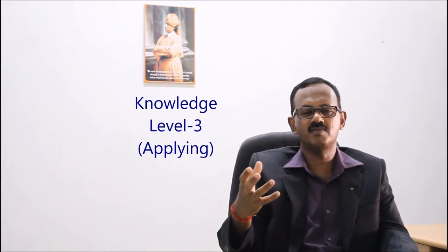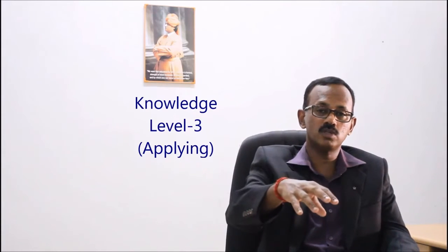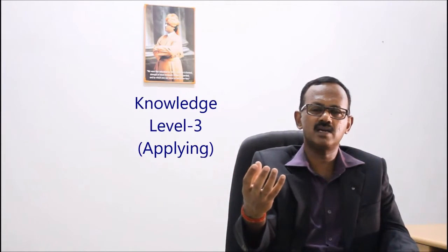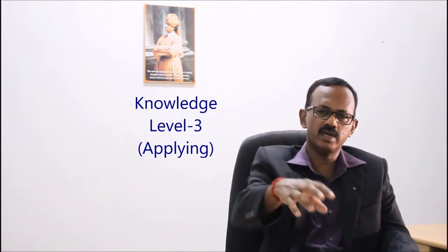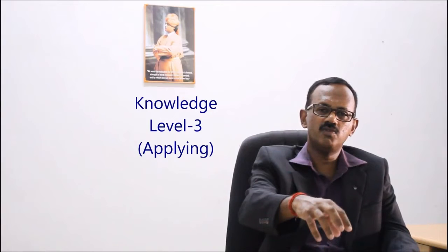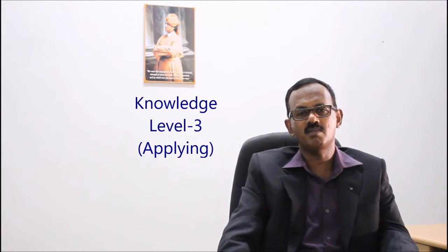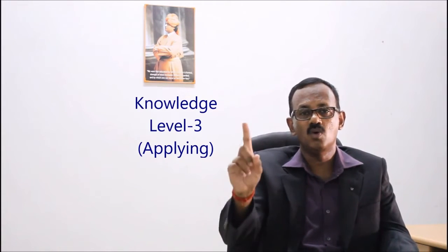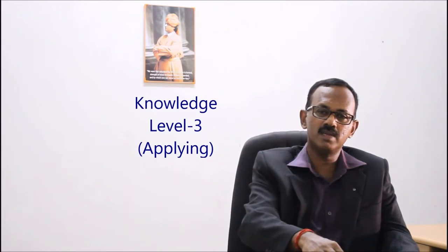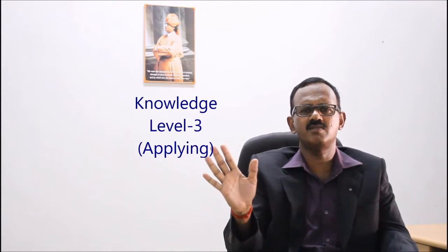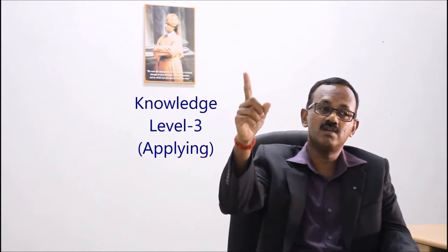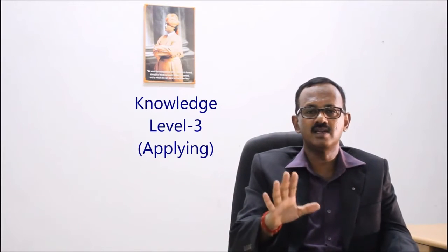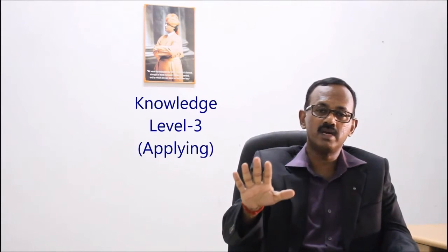Now, by the definition of calibration, when a known input is being given, that is, you take a 1 kg weight, and it should either be a primary standard or a secondary standard. Let us say you are going to take a 1 kilogram weight, and if you are going to place it on the weighing platform, automatically the reading in the digital scale is expected to be 1 kg, because you are placing either a primary or a secondary standard. That is, the exact weight will be there. Now, if the display shows below 1 kg or above 1 kg, then there is something required to be done in the system.